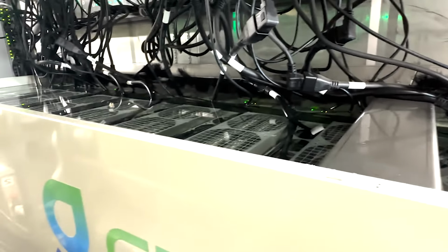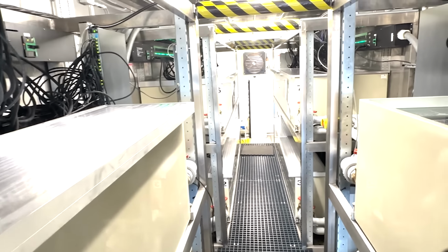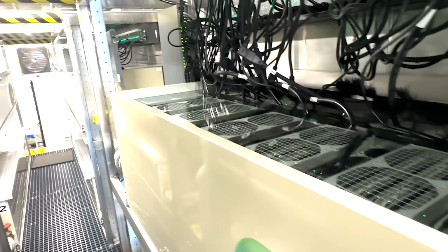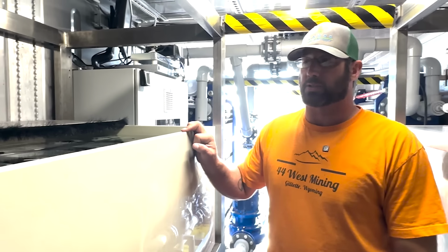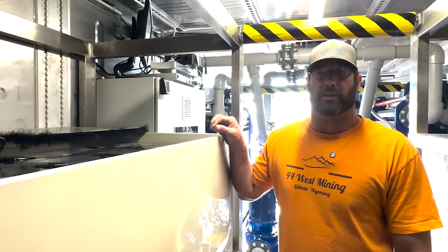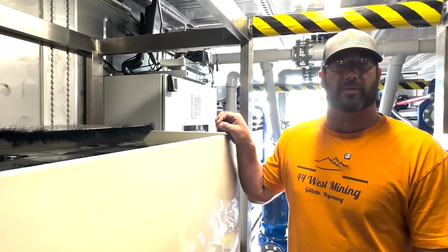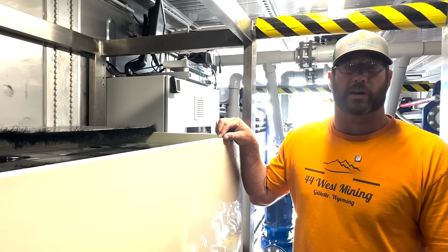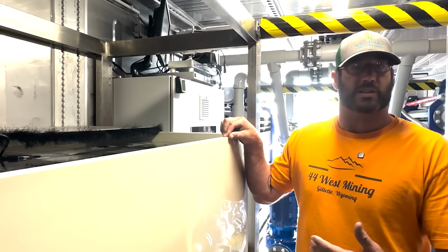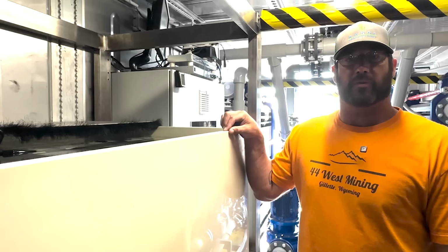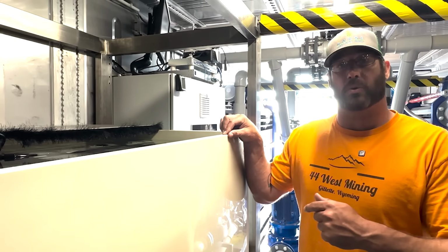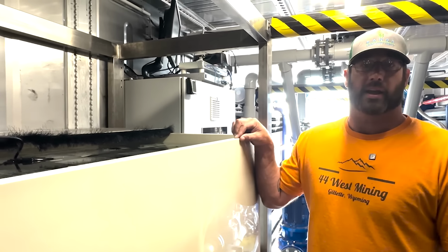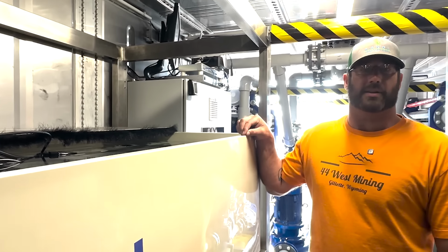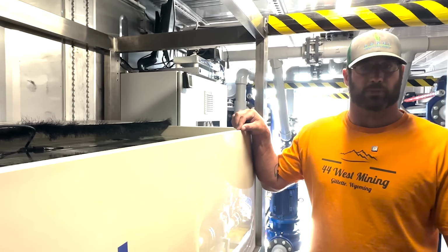Each one of these tanks holds 30 Bitcoin miners, and there are 8 tanks in total in here, for a total of 240. They each consume about 4,000 watts, so this container is close to 1 megawatt worth of power. The interesting thing that's different about Bitcoin mining compared to any other kind of data server is you can shut these off at a moment's notice and it won't affect the network at all. So as a demand response to grid balancing, if the power we're consuming is needed somewhere else, we can shut off.